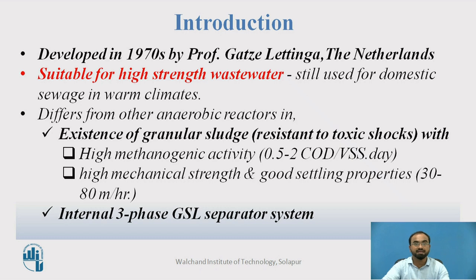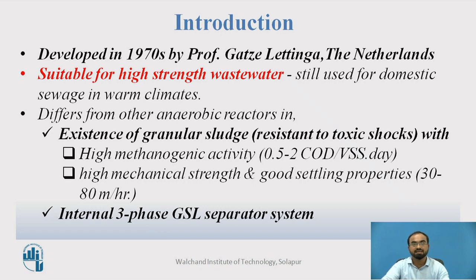It also differs from other anaerobic reactors. First, the existence of granular sludge that is resistant to toxic shocks, which has very high methanogenic activity — that is 0.5 to 2 kg COD per VSS per day — or high mechanical strength, or good settling properties, that is 30 to 80 meters per hour. Such a system will always provide the highest amount of anaerobic digestion relative to normal anaerobic digestion. It also has an internal three-phase GSL separator system, that is gas, solids, and liquid separator system. By combining these two features, UASB is normally considered much superior for anaerobic treatment.